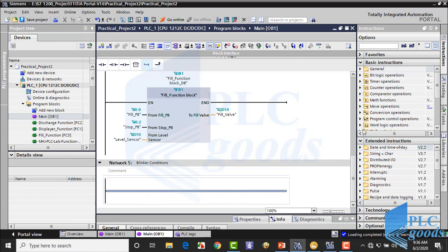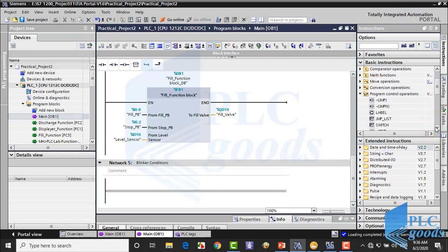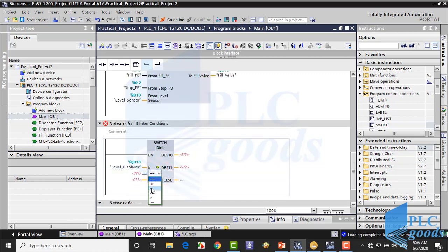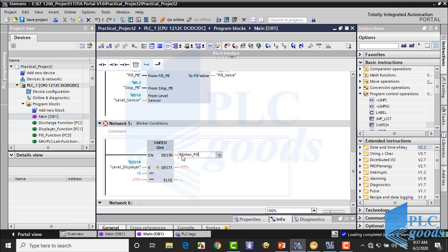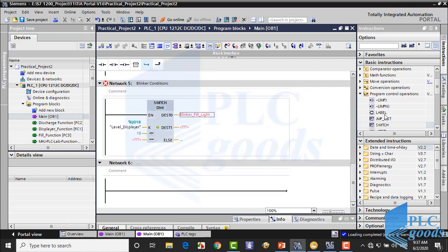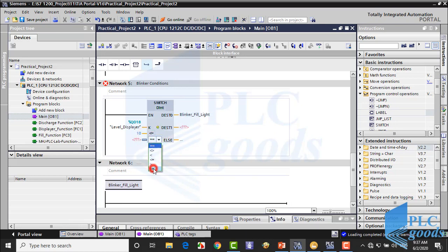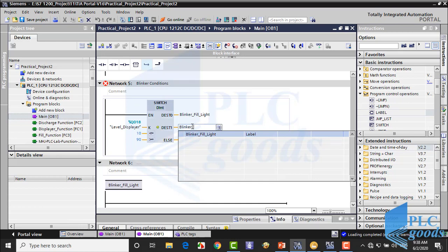At this network, I'm going to insert conditions, so let me insert a switch instruction. When the QD18 address — in other words, the liquid level — is less than 10%, the program will jump to a specified network. I use the 'blinker fill light' label for that. Also if the liquid level is greater than 90, the program will jump to another network with the 'blinker discharge light' label.